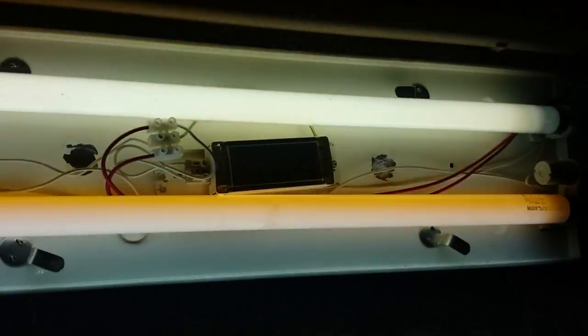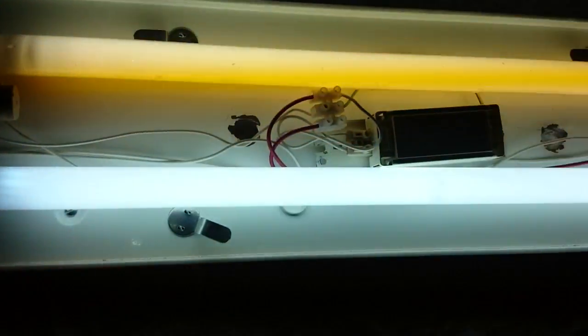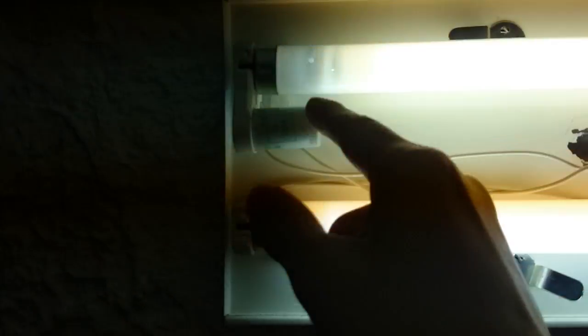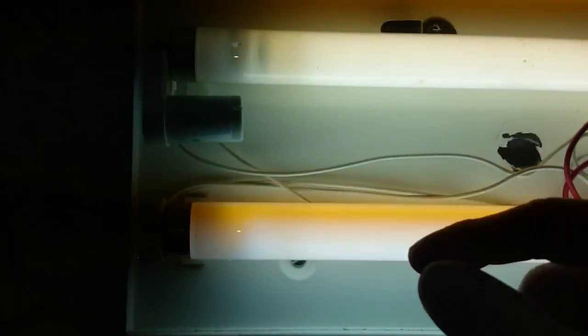Find out if your fluorescent bulbs are single or in series, because for example this one is made for series. If you replace it with a starter that's made for a single bulb, that wouldn't work and you would think it's defective, but in reality it's just the wrong starter.